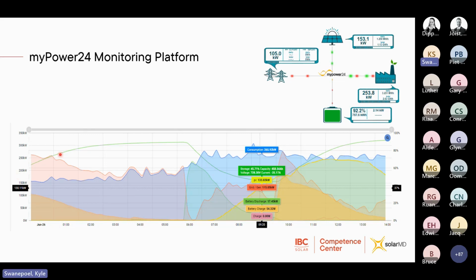This is completely scalable. You can view up to 7 days worth of data in one screen, but you can scroll back indefinitely as long as the logger has logged that information. And you can go and see that 10-minute data point, what was happening at that specific time, what the consumption of the site was, what the storage, the battery capacity was at, the voltage, what PV generation was happening. Here was the grid import. And then because this is a 10-minute data point, in that time, the peak was 54 kilowatt for charge and 17 kilowatt for discharge.